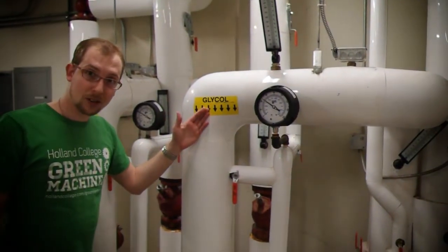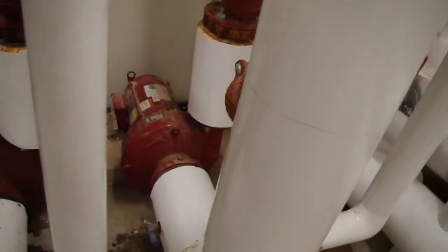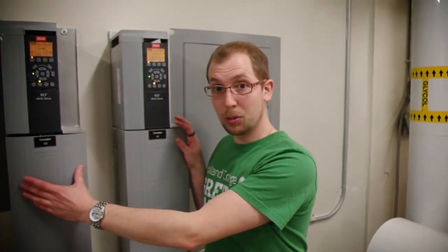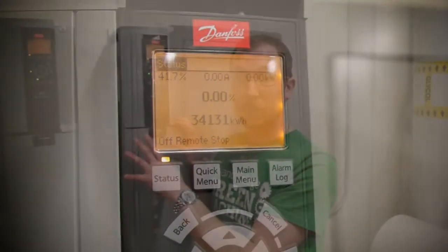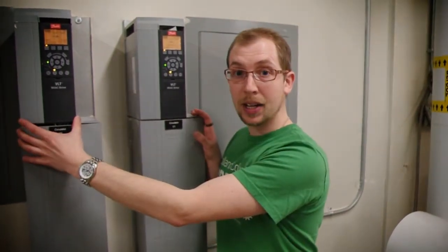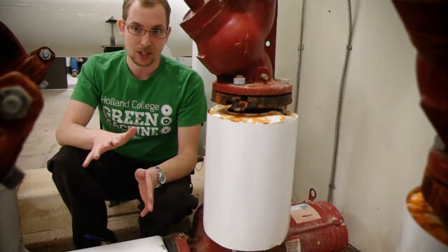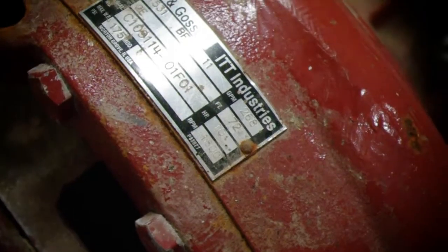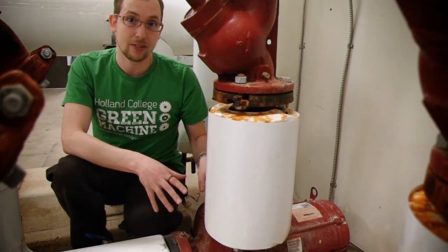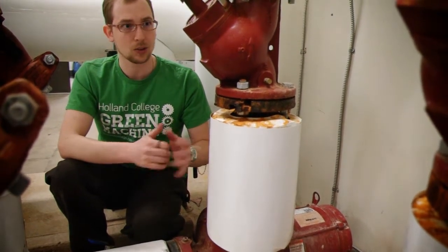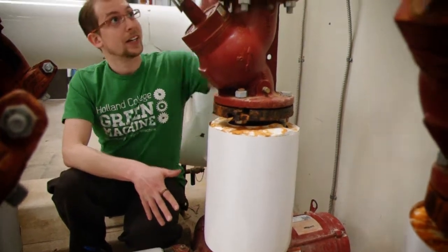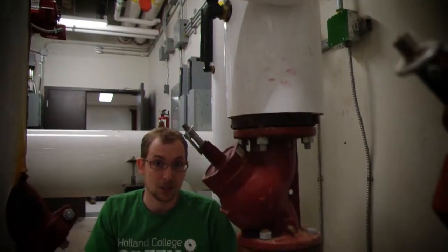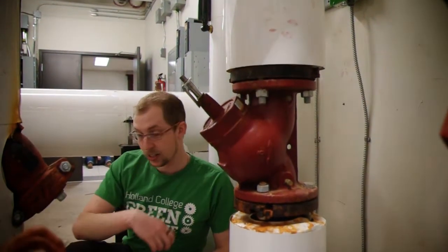It goes down exactly where the arrows state, and it's going to go down into a variable pump drive system. So right here are the brains of the operation for our variable frequency drive pumps. Both these are the controllers that operate the pumps themselves. So from here, an operator can come in, either shut them off, turn them on, monitor their usage. This one's the primary one, this one's a backup. It's hardly ever on. As previously mentioned, the variable frequency drive system that you can see right here acts very much like a light switch dimmer that you'd have in your house, so it can balance it out and saves power as well. So the fluid passes through that and it gets pushed up into this pipe here where it continues on, and it's going to go into one of our many heat pump systems supplied in the building, and I'm going to take you over here and I'll show you one of those right now.